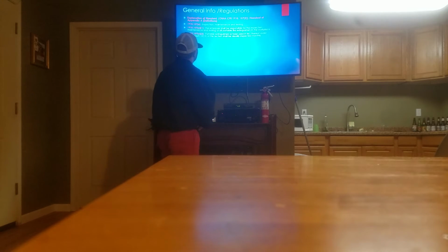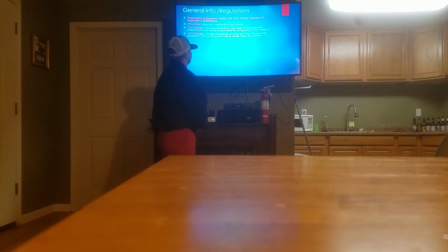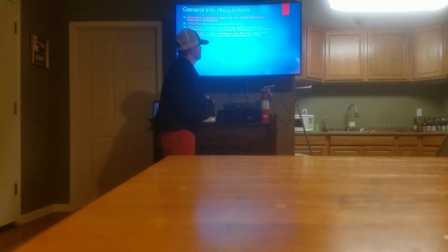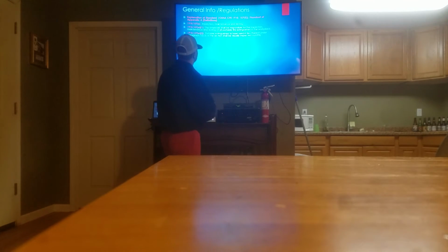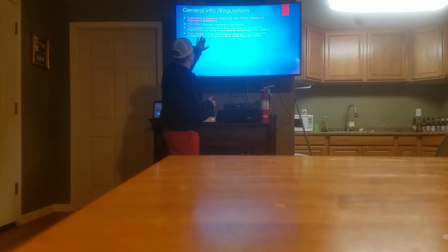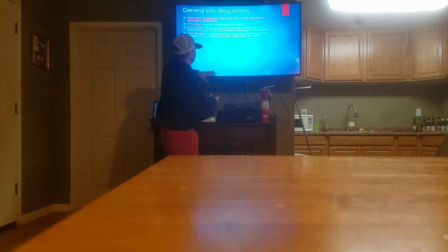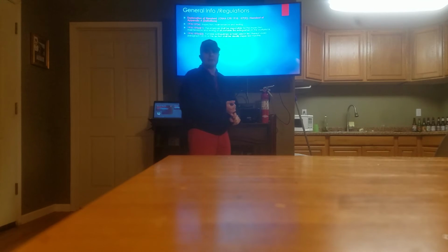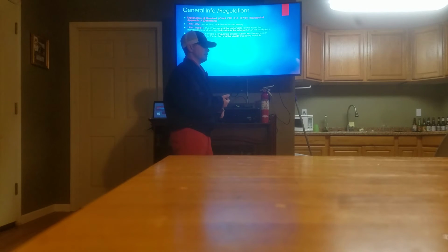Part 2. Portable extinguishers or hose used in lieu thereof under paragraph D, number 3 of this section shall be visually inspected monthly. So a lot of times with these OSHA regulations and standards, you really gotta dig through them and do some research to understand what they're saying. This part right here is not on this slide, it was in the standard itself. This was saying that all your standpipe or your fire water header system needed to be inspected monthly.